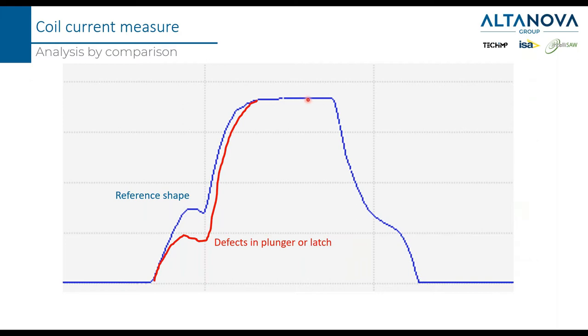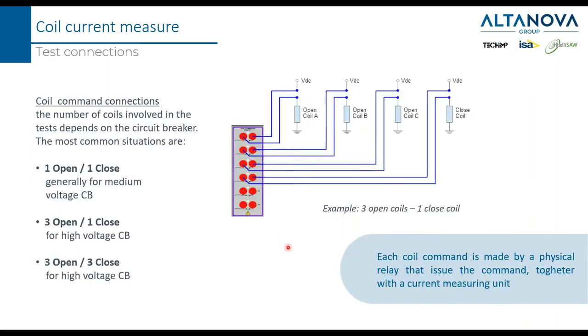To measure the coil current, you need a device connected in series to the coil. In our connection scheme, we connected three open coils — one for phase A, one for phase B, one for phase C — and one close coil. In such a situation, the close coil means it is operating all three phases together.